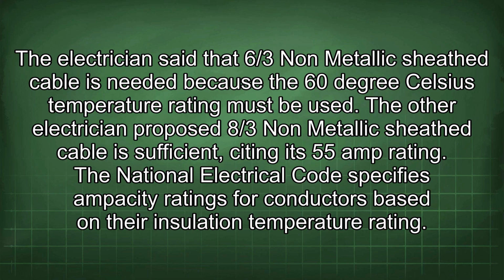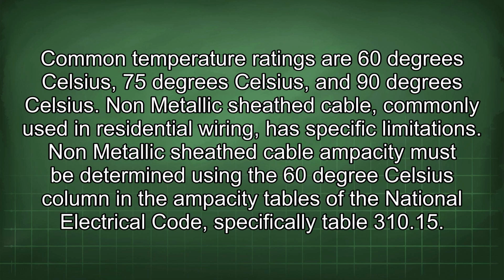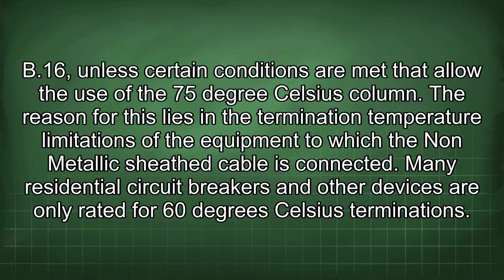The National Electrical Code specifies ampacity ratings for conductors based on their insulation temperature rating. Common temperature ratings are 60°C, 75°C, and 90°C. Non-metallic sheath cable, commonly used in residential wiring, has specific limitations. Non-metallic sheath cable ampacity must be determined using the 60°C column in the ampacity tables of the National Electrical Code, specifically Table 310.15(B)(16), unless certain conditions are met that allow the use of the 75°C column.